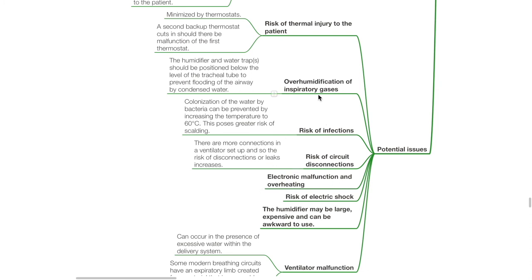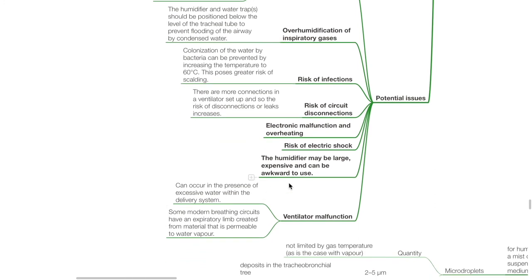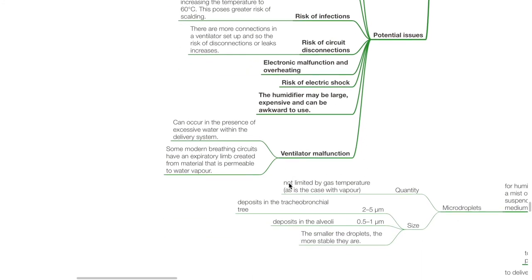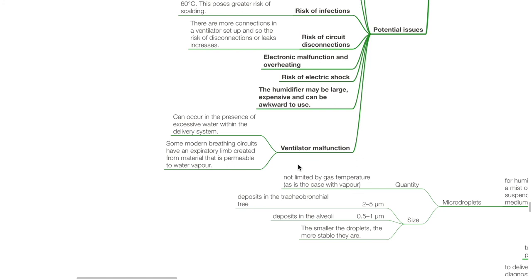Potential issues of the hot water bath humidifier: risk of thermal injury to the patient — minimized by thermostats; a second backup thermostat cuts in on malfunction of the first. Overhumidification of inspiratory gases. The humidifier and water traps should be positioned below the level of the tracheal tube to prevent flooding of the airway. Risk of infections: colonization of the water by bacteria can be prevented by increasing temperature to 60°C, though this poses a greater risk for thermal injury. Other risks include: circuit disconnections, electronic malfunction and overheating, risk of electric shock, the humidifier may be large, expensive and awkward to use, and ventilator malfunction can occur in the presence of excessive water within the delivery system.